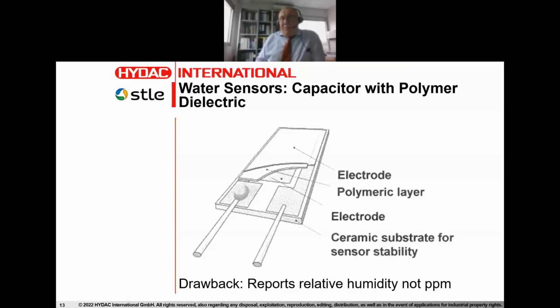And moreover, the relative humidity is going to change with temperature, and that's even when the system is closed, not only when the system is open. When the system is open and the water evaporates, that makes it even worse. But when the system is closed, the relative humidity is going to change simply as a result of molecular motion. Molecules move further apart from each other, so the number of water molecules per unit volume of the lubricant decreases, and hence the relative humidity goes down. But it does not tell us that we actually have removed or added water to the system, which can be misleading. If we don't know if the water is ingressing into the system or egressing as a result of condensation, or egressing from the system as a result of purifier functioning.